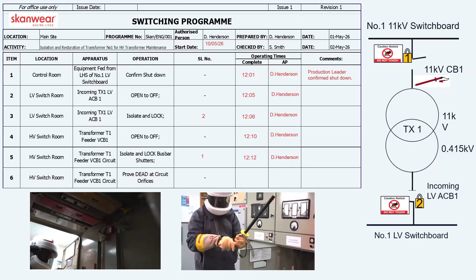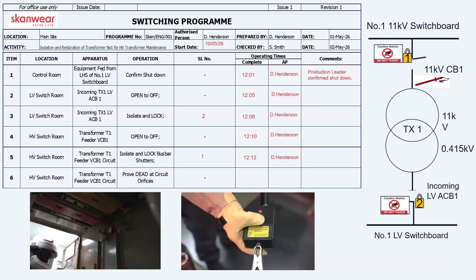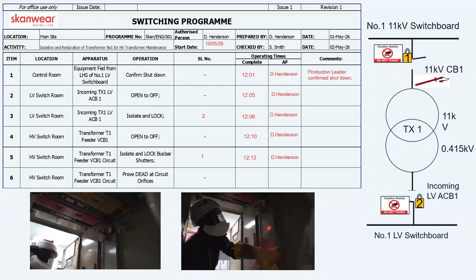So we're going to check our instrument, our potential indicator, to make sure there's no damage to it, that it's been calibrated, and it's in good condition. We're then going to check it against a safe voltage source, so a proving unit ideally. We're going to connect to ground. We're then going to check each phase, looking for a go or no go, so the indicator isn't illuminated, indicating that there's no voltage present. On completion, we'll prove the instrument again using the safe voltage source, the proving unit, to make sure that the instrument hasn't failed in operation and that it's still functional. So based on that, we've taken all reasonable checks to make sure that there's no voltage present.